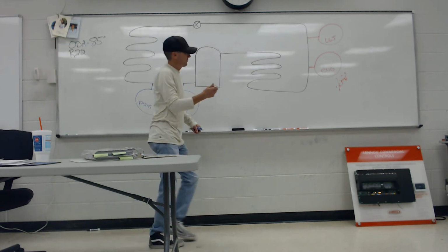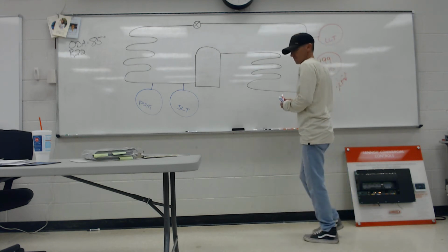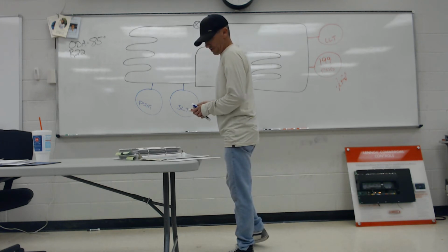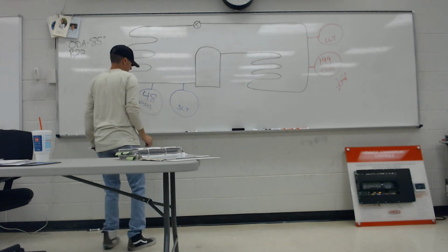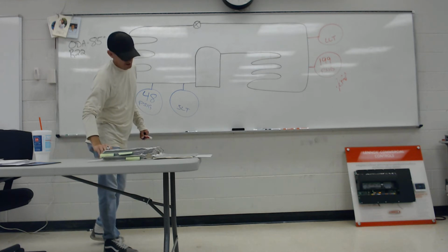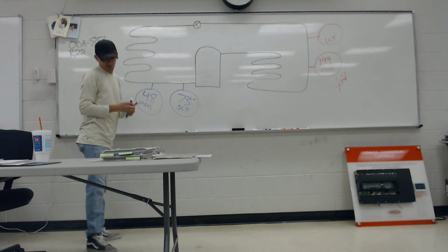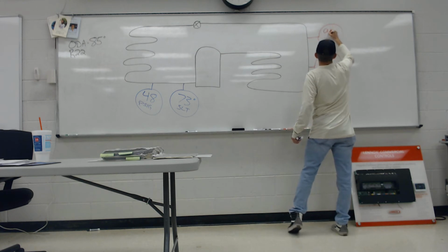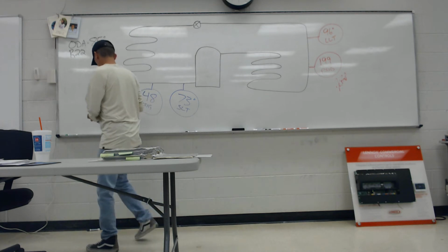Head pressure is exactly 199, and suction pressure is 48. Suction line temperature 73, and 96 on the liquid line. You want any more information?